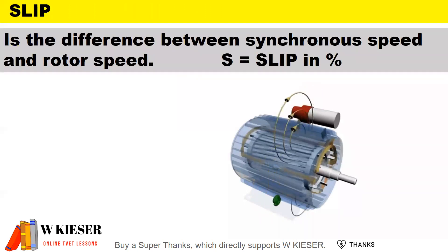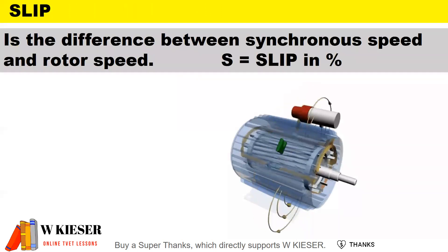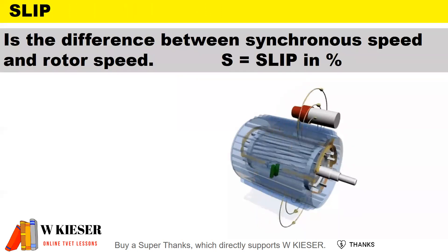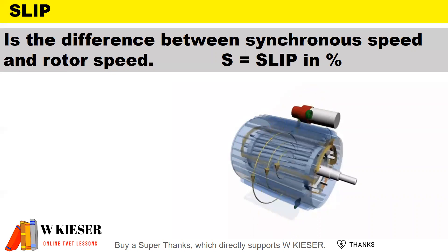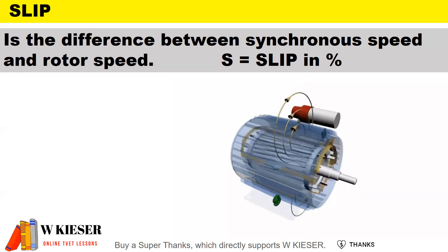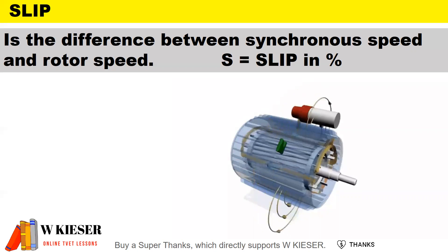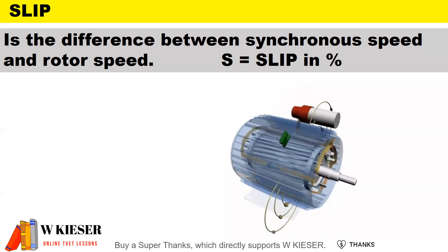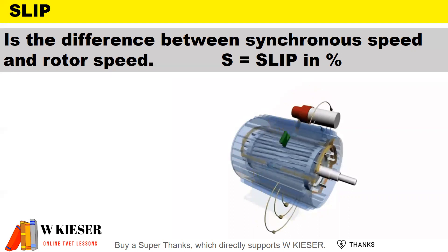To define the term slip: slip is the difference between synchronous speed and rotor speed — in other words, the speed of the rotating magnetic field versus the speed of the rotor. In order for EMF to be generated, there needs to be a difference in speed between synchronous speed and rotor speed, and this is represented as a percentage called slip.